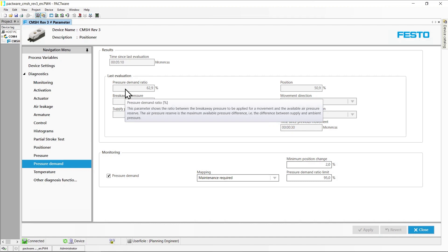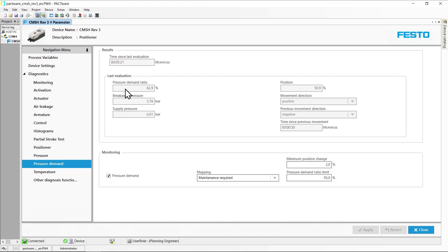100% would mean that the breakaway pressure difference equals the difference between supply pressure and ambient pressure. The pressure demand ratio is calculated in slightly different ways depending on the actuator type and direction of movement. Details can be found in the DTM documentation of the CMSH.